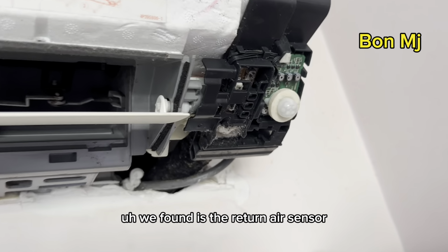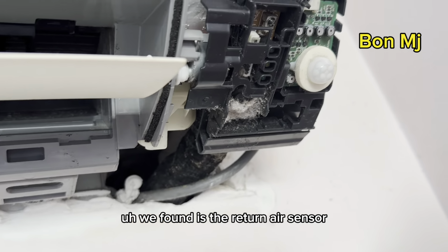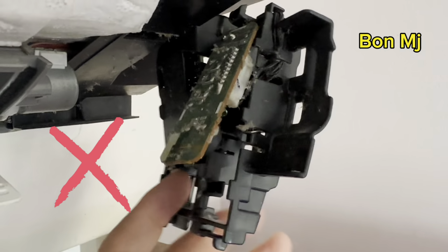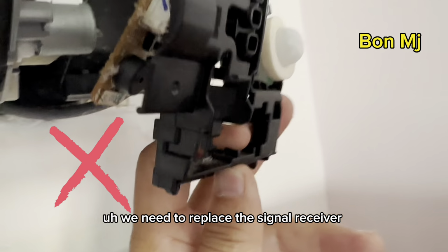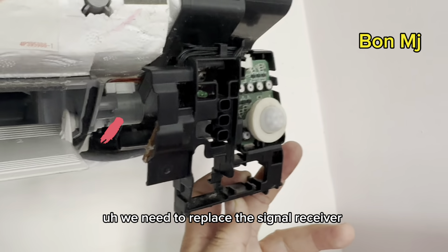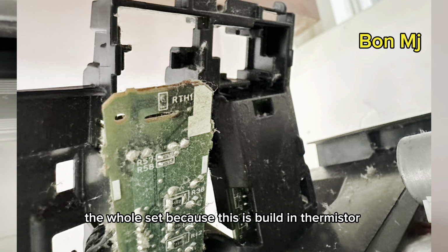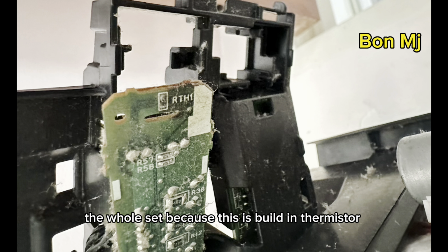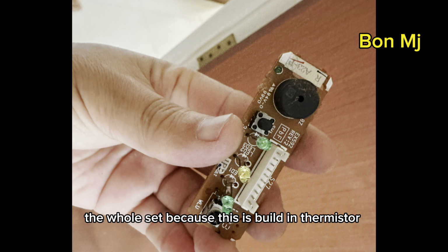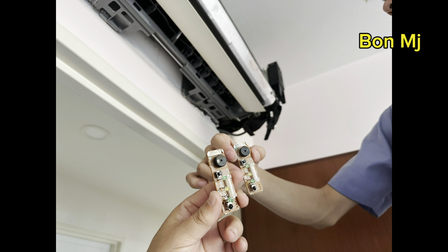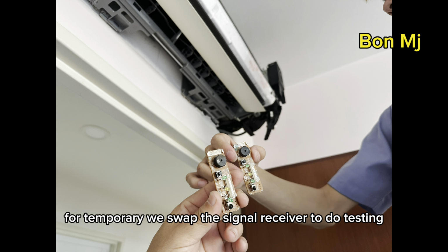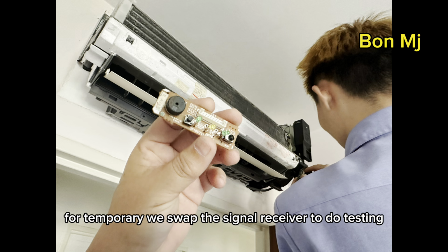We found that the return air sensor temperature is 4 degrees lower than the others. We need to replace the signal receiver, actually the whole set, because the thermistor is built in. For temporary, we swap the signal receiver to do testing.